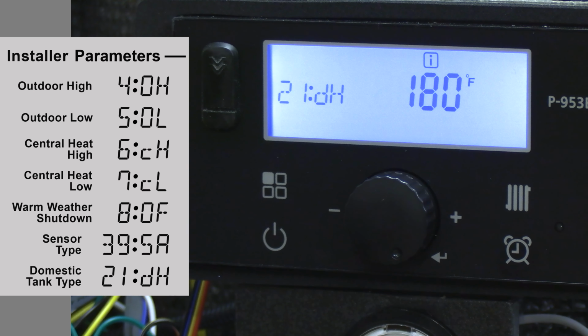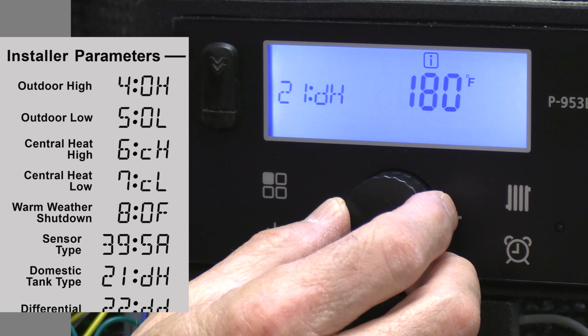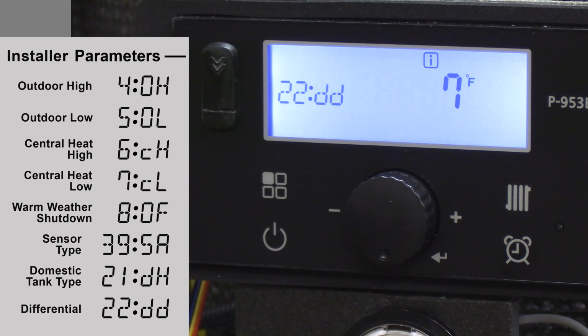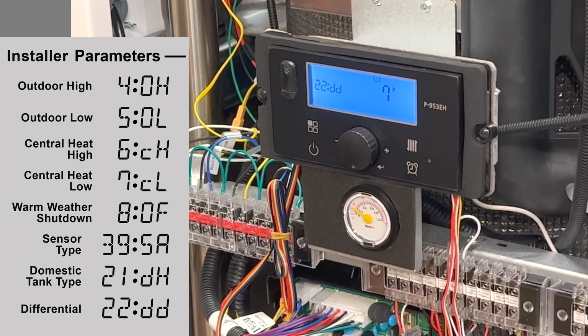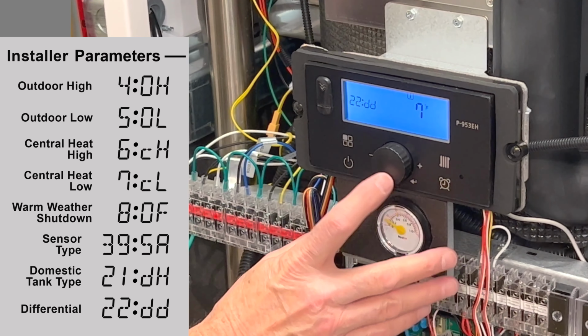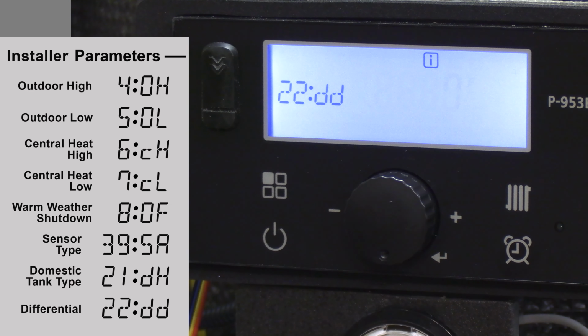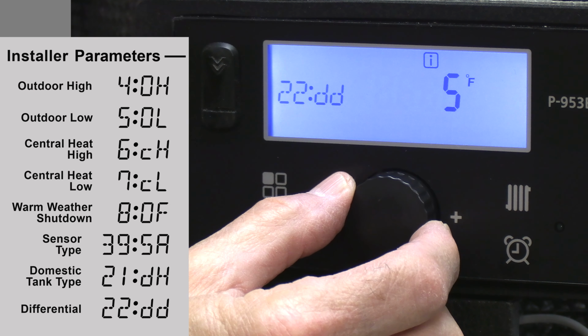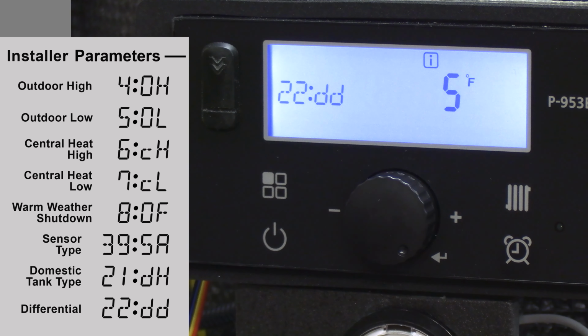All right. If I'm using an actual sensor, then I would set that up at 120 or 130 or 140, depending on what the sensor was. And then lastly here, we'll go to parameter 22. And this is your differential, okay? It's defaulted for 7 degrees. The range is from 5 to 30. So as an example, I might only want a 5-degree differential, so I'll bring that back to 5, press and hold that, and I've stored it.